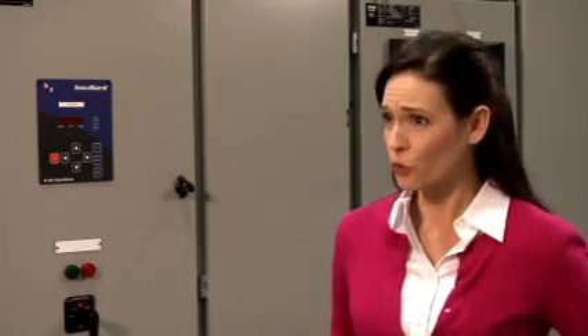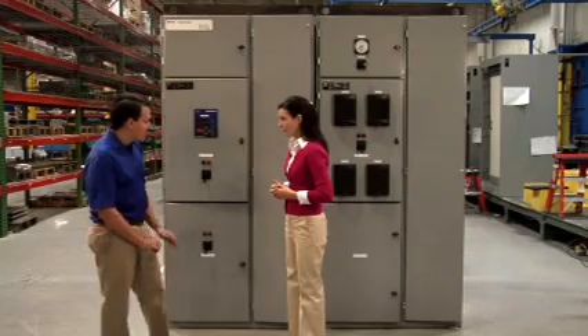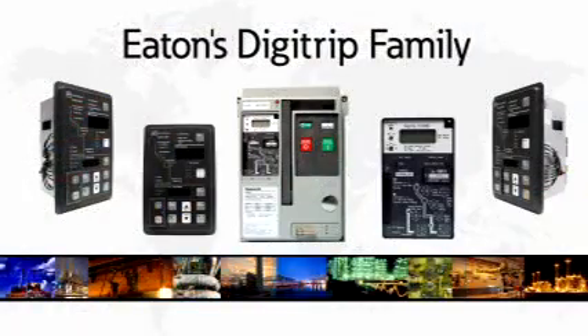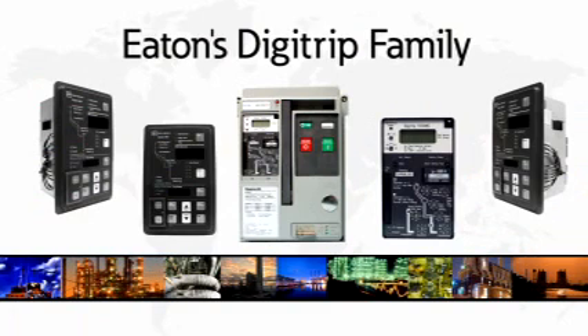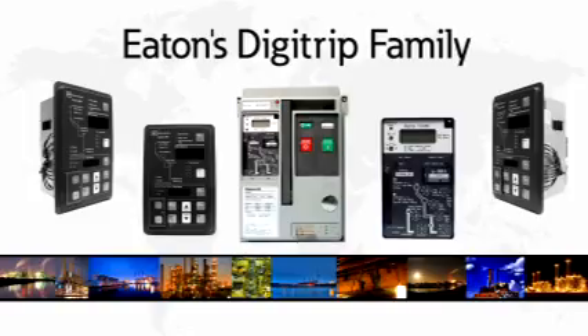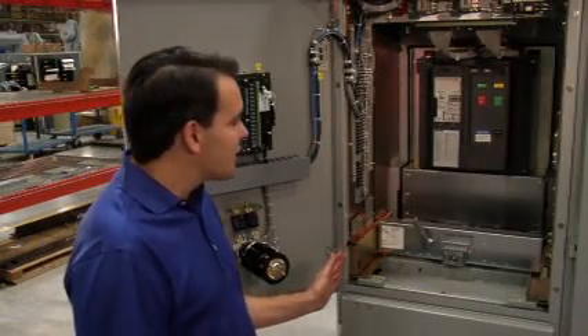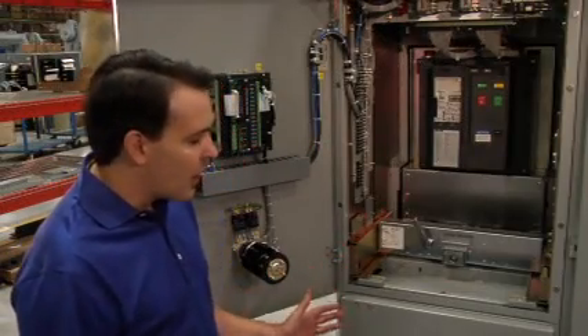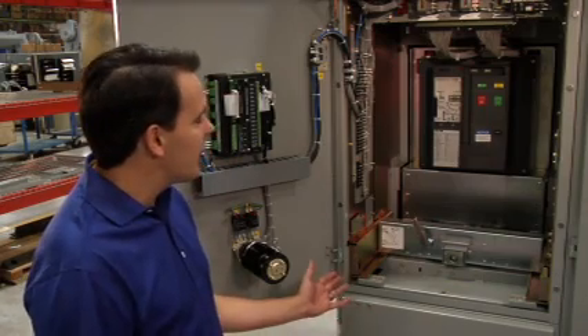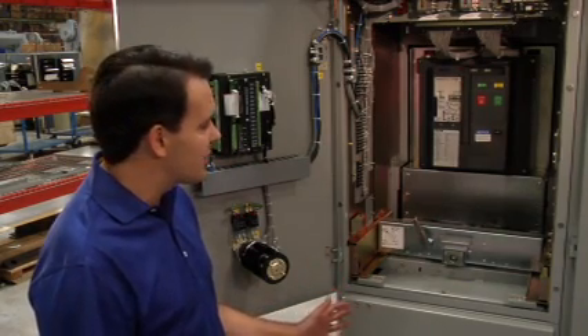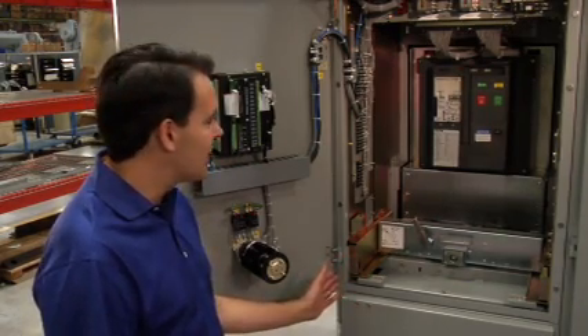Now let's go topside here and look at the trip units. We have an integrally mounted Digitrip, but the customer can specify any range of external trip controls, right? Sure. As you mentioned, we have the integrally mounted trip units, which I just pointed out. That's our Digitrip family. We also have externally mounted Digitrip trip units. The integrally mounted trip unit is nice because it's self-powered. If the power goes out and comes back on, you know that the trip unit has power to protect you downstream because it's getting its power from the main circuit.